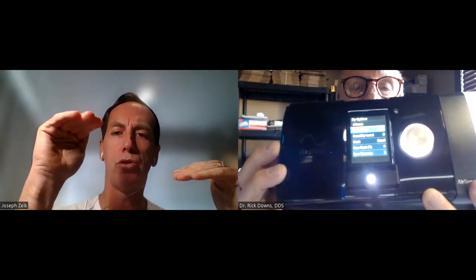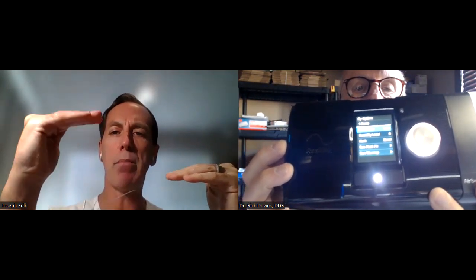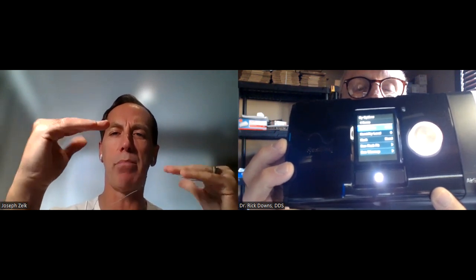And it will also allow you to extend the amount of ramp time. So what is ramp? Ramp means that the pressure starts low, so it's less uncomfortable. And over a period of time, it'll gently ramp up to the treatment pressures, which are a bit less comfortable. Your sleeping brain technically should be able to tolerate that, but your awake brain might find it's a little uncomfortable.